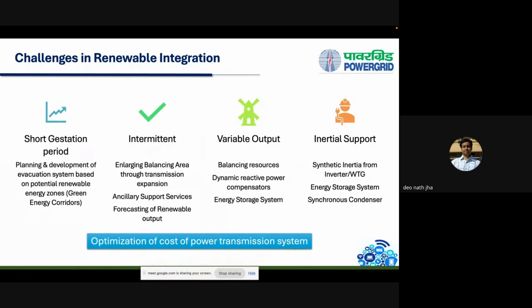But the challenges with renewable integration are that it has a very short gestation period, so there's a need for planning and development of evacuation systems based on potential renewable energy zones. An earlier speaker mentioned 15 to 20 years for a generation plant to come up, but renewable plants are coming up in about 6 to 10 months. So there's a very short gestation period from planning to development, and the corresponding transmission evacuation system also needs to be planned much earlier, because the transmission network takes about 2 to 3 years from planning to development. If both are planned together, transmission will lag behind and we cannot get the full advantage of that generation. So transmission networks have to be planned around 2 to 3 years before the generation needs to come up.